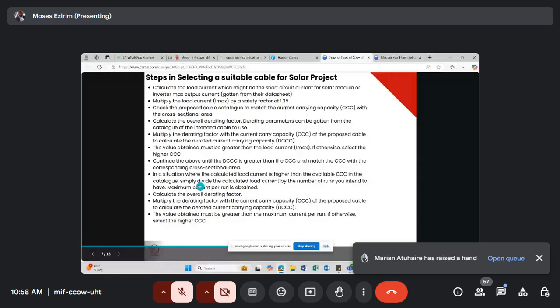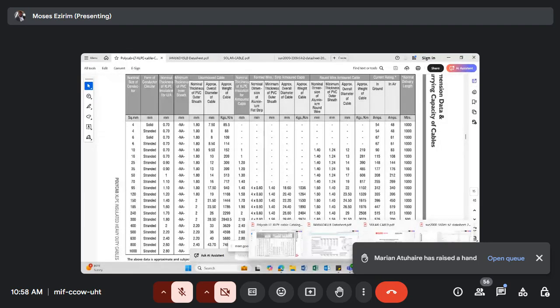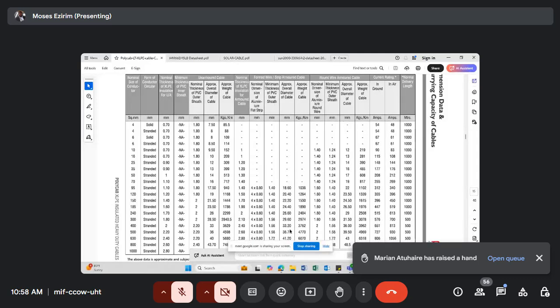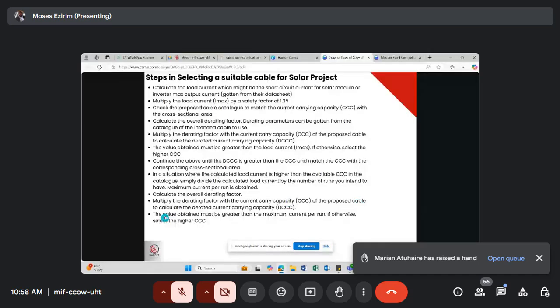So now when you divide, you get the maximum current per run, which we've gotten to be 480.6. Now calculate the overall derating factor, which I've assumed to be 0.7. Multiply that factor with the current carrying capacity, as we've been doing - but it's the 727 we multiplied with that's greater, and from the proposed cable we calculate the derated current carrying capacity. The higher the value, the higher CCC must be.